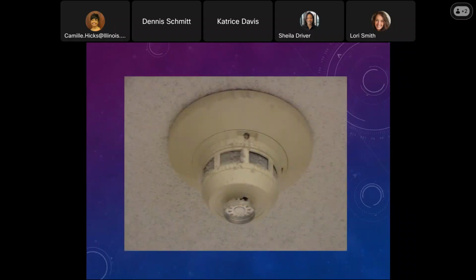This is another one. Many of you could probably guess where this is. This is actually in one of the laundry facilities inside a skilled nursing facility. Because of all the lint and dust on it, these smoke detectors must be cleaned. They must be inspected and cleaned, if not by the facility, then by the fire alarm contractor or a subcontractor that comes in and does these special cleanings. But those have to be cleaned because that also inhibits the smoke from entering the detector.